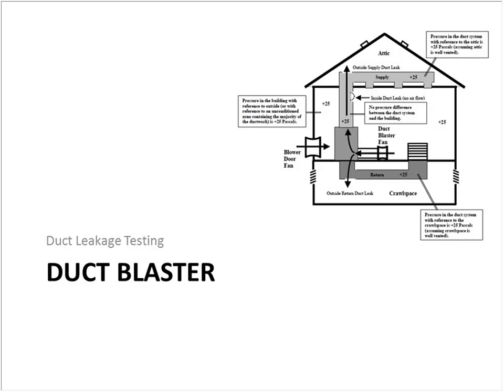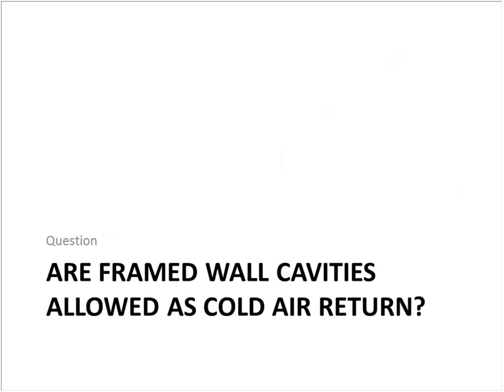It's very, very difficult to meet that standard of 3 CFM. So ideally, you would test it at the end if you're going to have ducts. Better than that, you would have all of your ducts in the bulkheads so that they're inside the thermal envelope and you wouldn't have to test. But there are situations, we had a situation yesterday where we had to test duct leakage because we couldn't verify the full R value was there, because they didn't invite us in for a pre-drywall inspection. So if there's any way that you can avoid those conditions, it would be a good idea to do that.